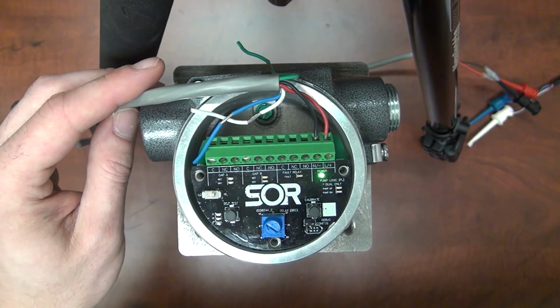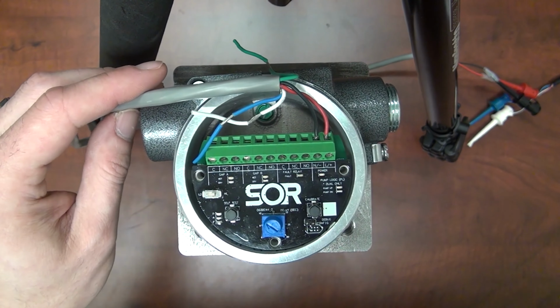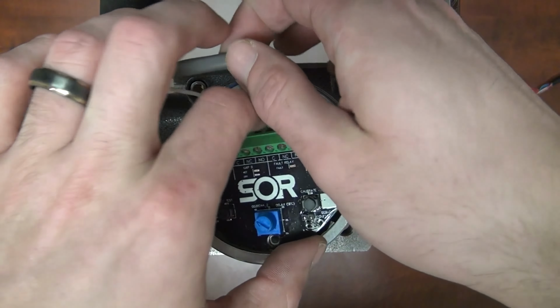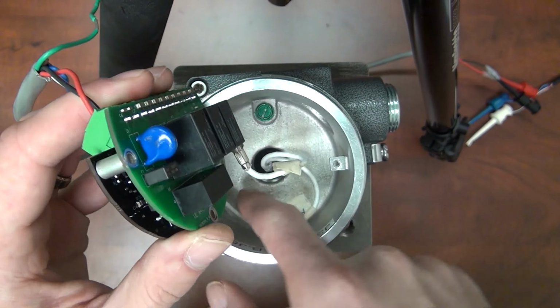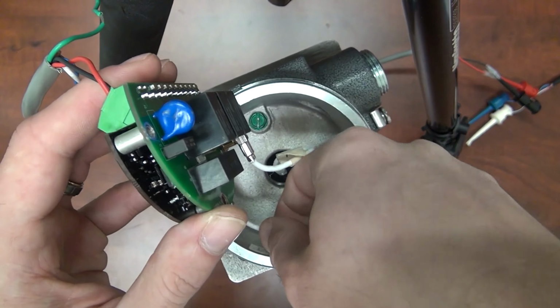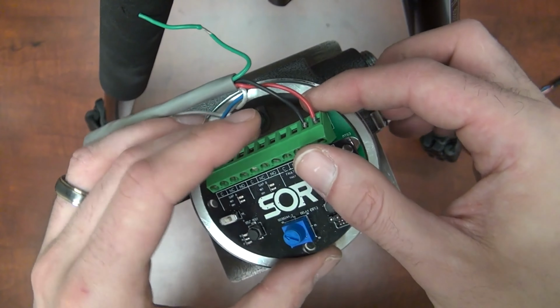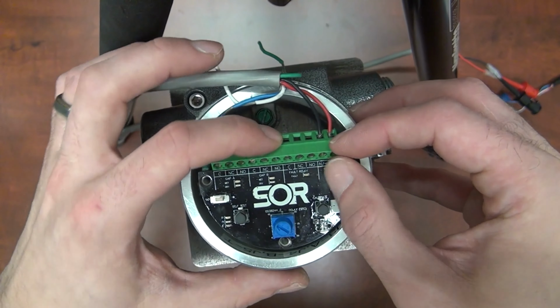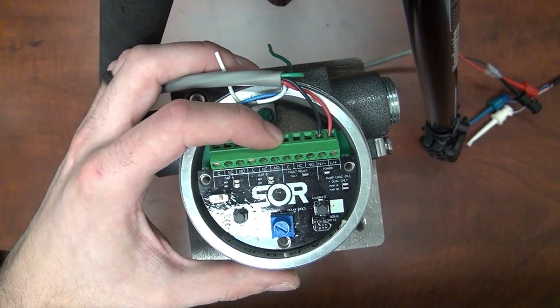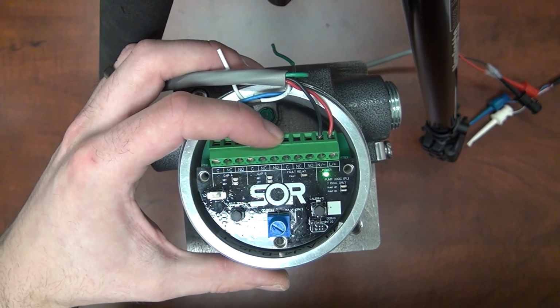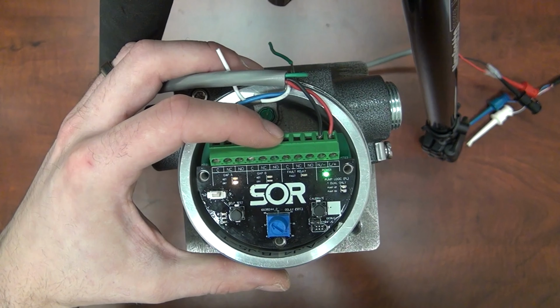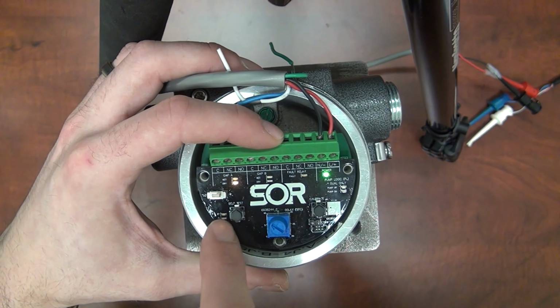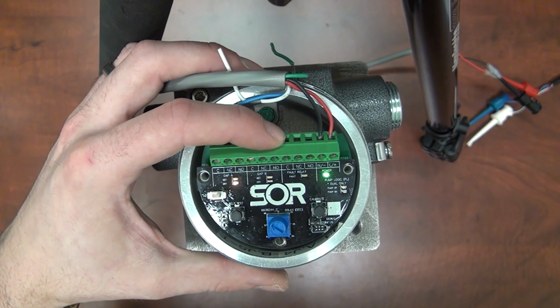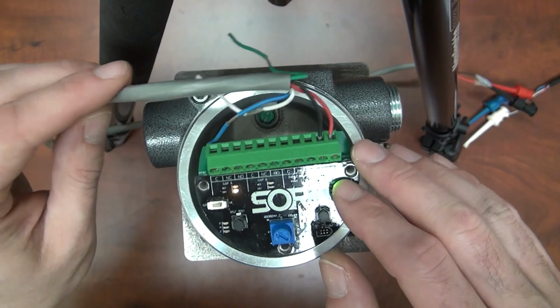Let's correct this. Let's turn off power to the device, undo our interface board, turn it back over to the power board, and now let's plug this A cable into the A connector. Now that the probe has been properly reassembled back to the electronics, let's power up the device and press the self-test button one last time. The device powers up and now it's in the normal operating mode. We press self-test and we'll see it will give the green passing LED result. The device is now operational and ready to use.